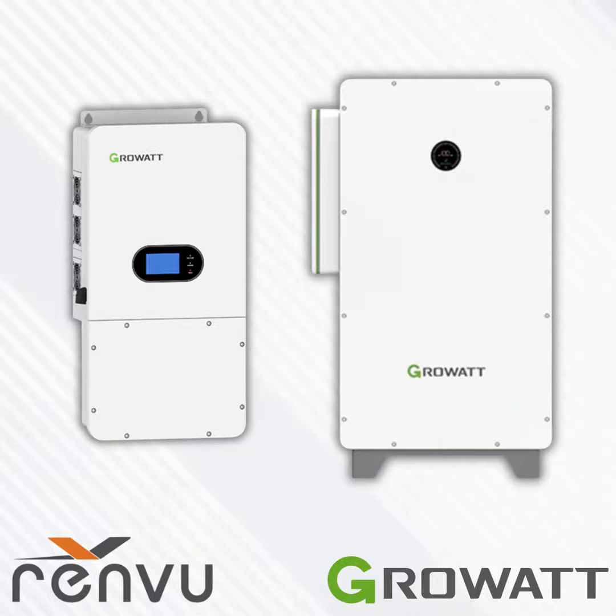On the right is the WIT. It's our hybrid inverter, and we have 2 series of inverter for this product. We have 28 to 55 kilowatts, which is broken up into a range. So there's product for 28, 35, 42, and 55. And that's a 208 volt 3-phase output. And then we have 50 to 100, which also has segments, and that's a 480 volt output. Both of these can be configured in 3-phase, 3-wire, or 4-wire, whichever one is appropriate for the project. 60 hertz, they're indoor, outdoor rated.